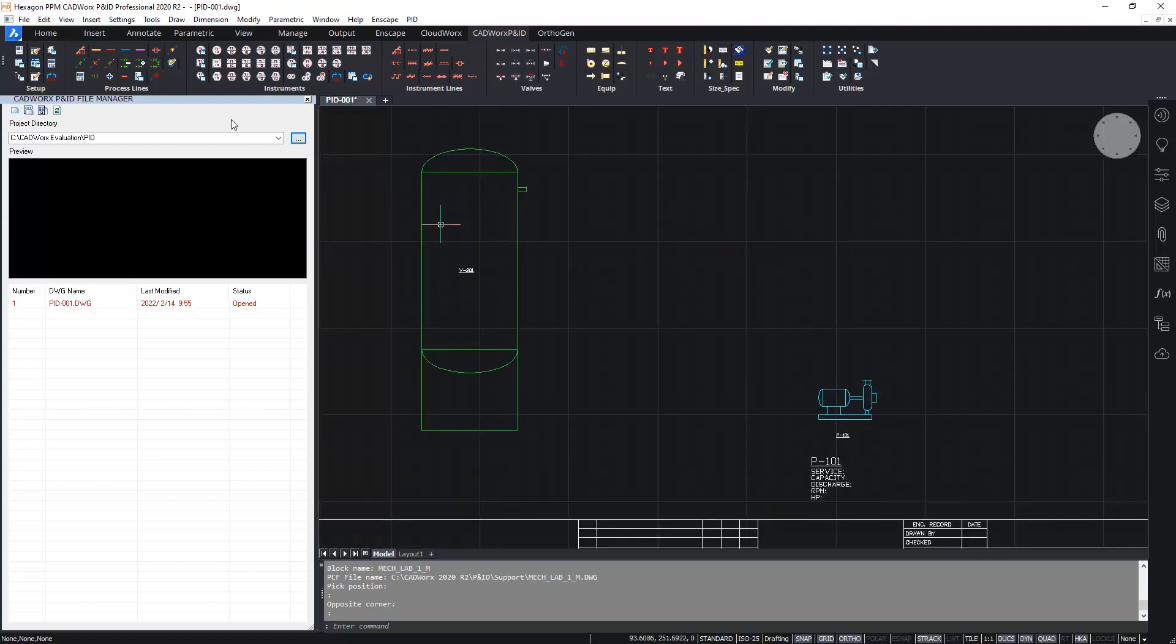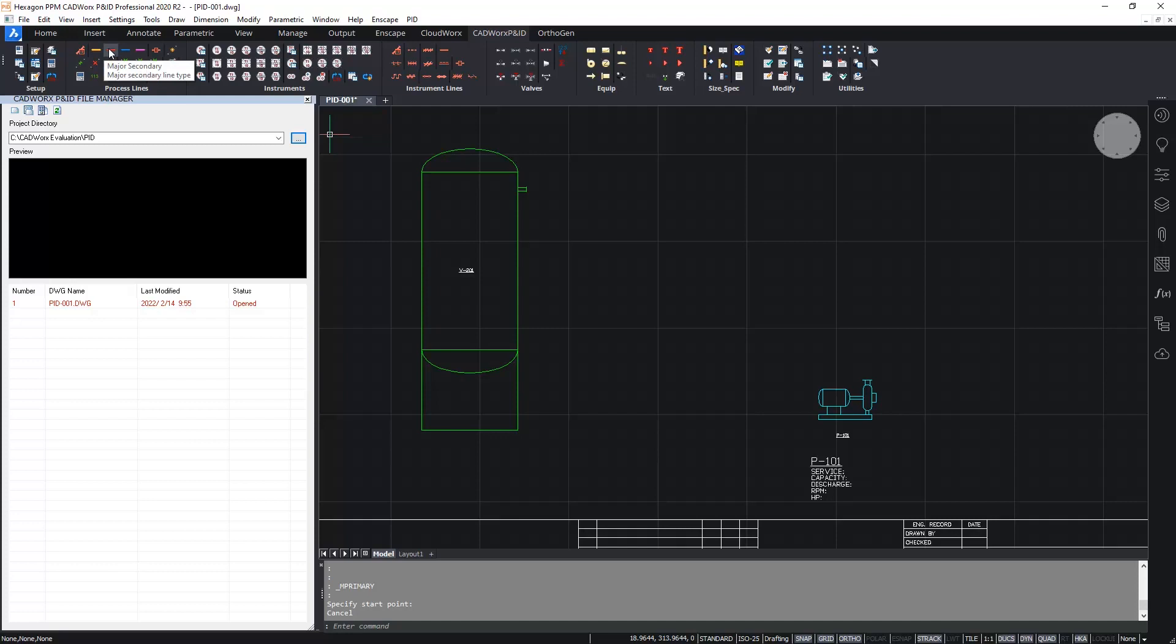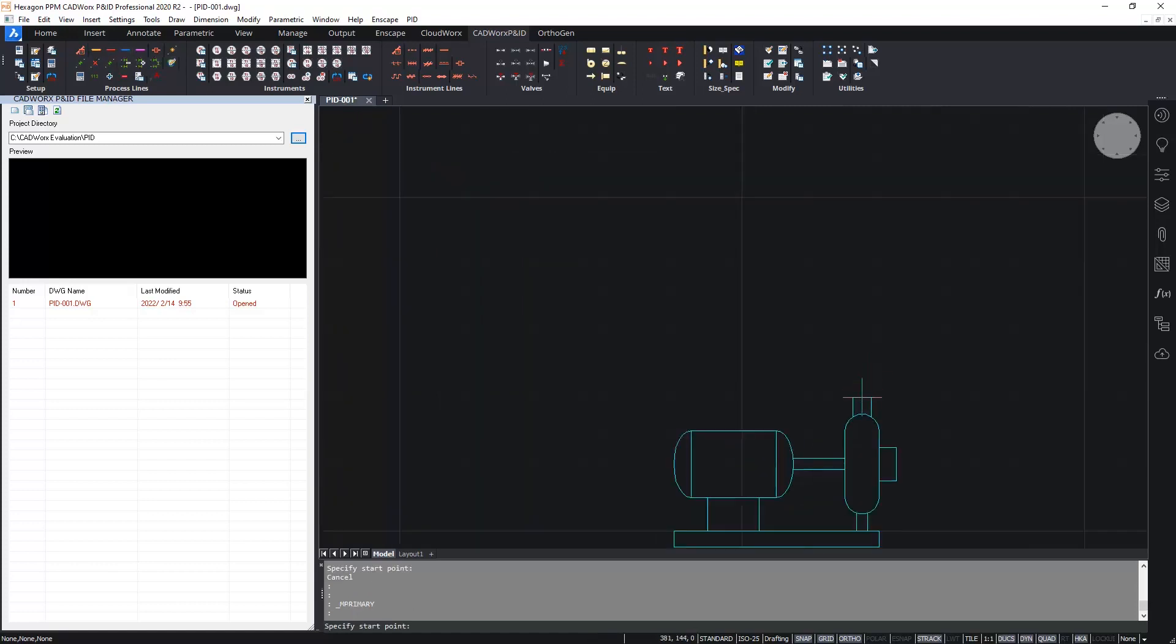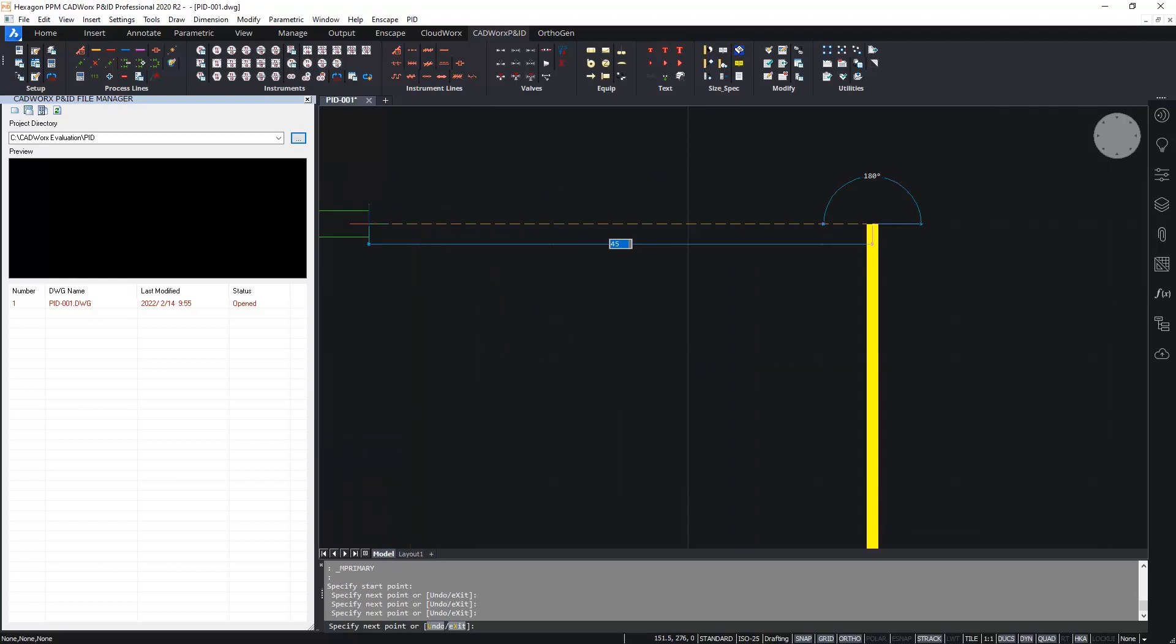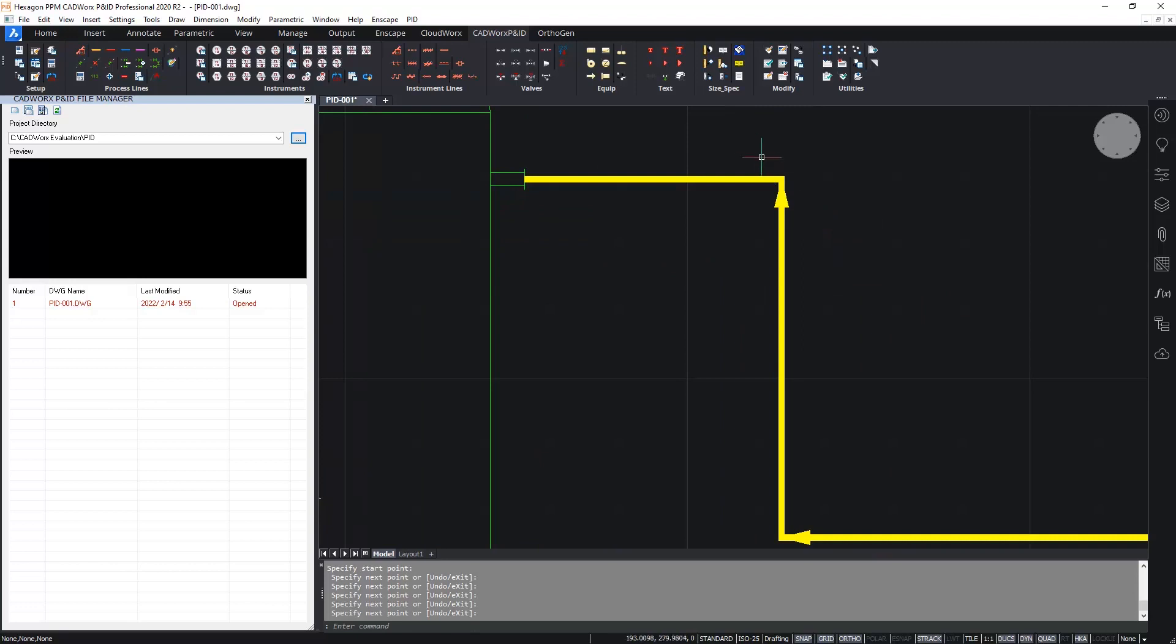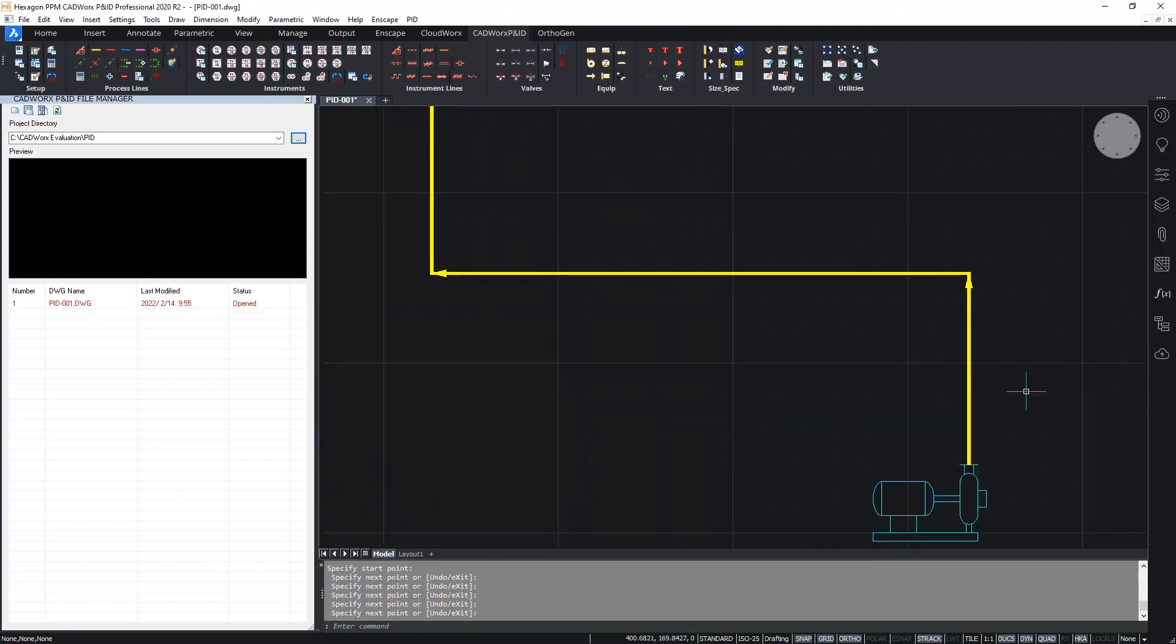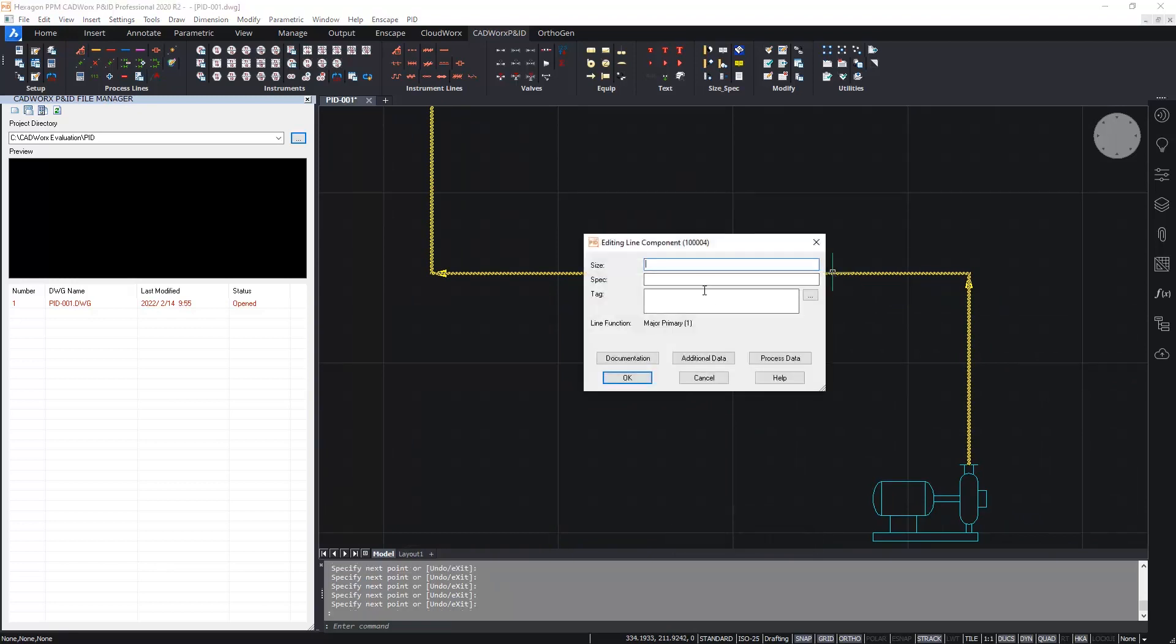Okay next in this simple P&ID I'll draw a process line connecting from the pump to the vessel from the pump discharge nozzle to the vessel. Again there are various different available lines within Cadworks. All completely configurable. The most commonly used lines though are these ones on the icons here. The major, primary and secondary and the minor, primary and secondary. I'll choose a major primary process line. And I'll start from the pump discharge nozzle and go across and connect up to the nozzle on the vessel. Once I hit enter to finish, as you can see, the flow arrows are placed automatically at each vertex of the line. And if I double click on the process line, I could then add a tag.